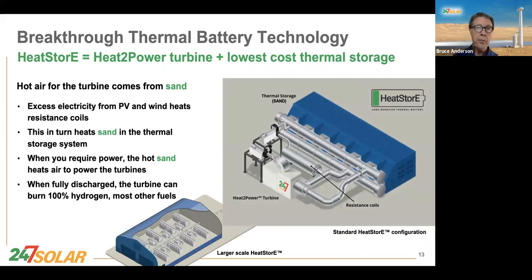Our breakthrough battery combines the heat storage, which is very, very cheap, and that turbine. The heat storage is this container here, about the size of a shipping container. It's shipped to the site empty and then filled with sand. Excess electricity from PV or wind heats electric resistance coils, which heat air, which heat the sand. Then, when there's a demand for electricity, the air is pulled through the sand, is heated, and that's brought to the turbine for producing electricity without any combustion, just hot air.